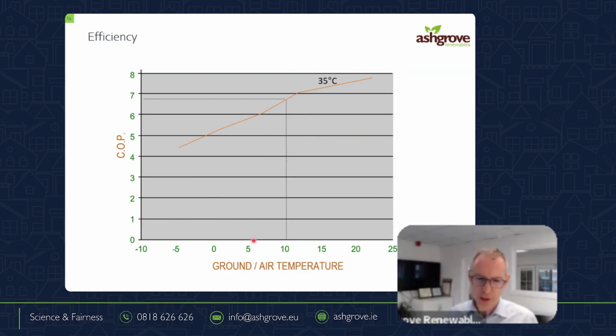But if I travel down along here until it gets to -5 outside, you can see my COP here now is at whatever that is, 4.4 or whatever it is. So the outside air temperature or ground temperature will affect my efficiency, right? So you can see it's quite a dramatic drop to the left. More importantly, you can do nothing. You can't control the outside temperature, but you can control the operating temperature. So if I have underfloor heating and I'm working at 35 degrees there, you can see that I am operating at we'll call it 7 of a COP. Whereas if I'm at radiators and I need to run to 50 degrees, you can see there I'm after dropping to 5.